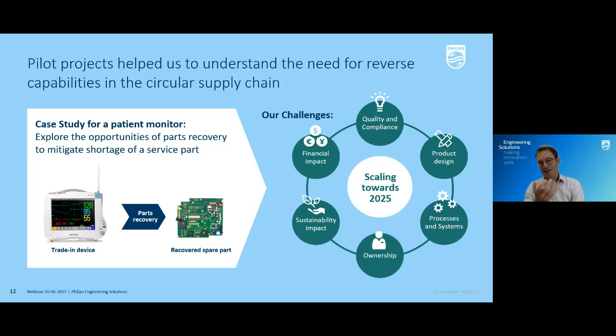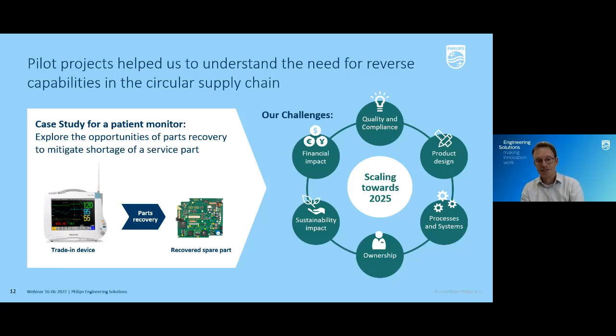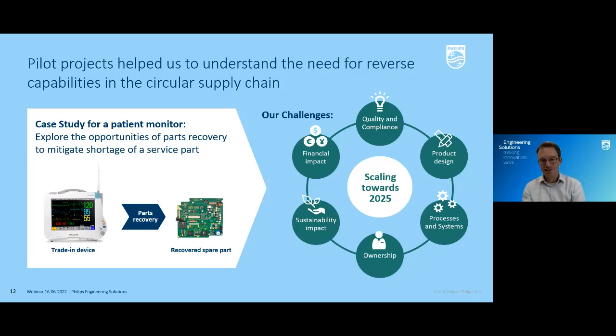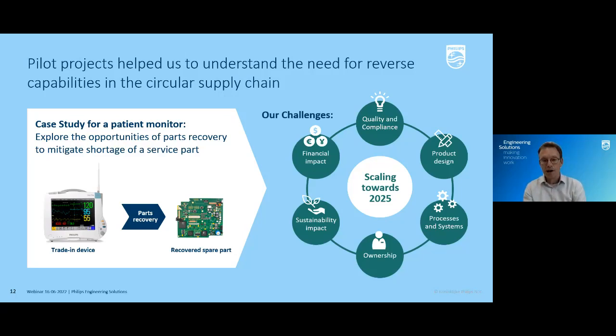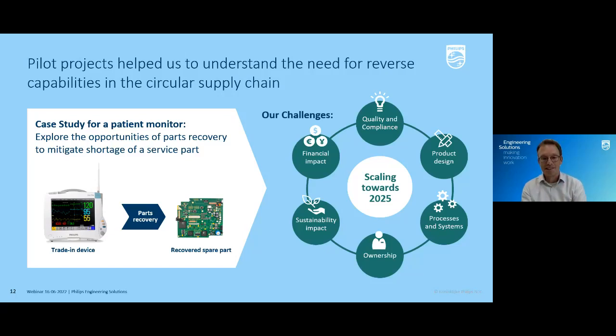Starting with quality and compliance: we are reusing used materials, and in Philips' case in medical applications, we must be fully sure that whenever we reuse, we comply with all quality and regulatory requirements. In this pilot case, we were lucky — the spare part was designed as a repairable spare part, so we were good to go. But for other parts that have not been defined as such, there's a challenge, which also brings us to product design.